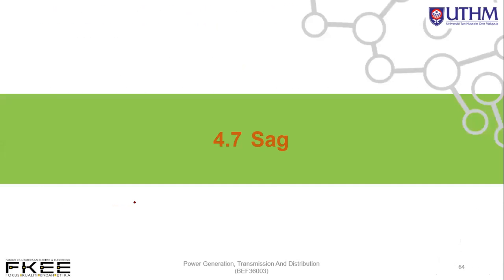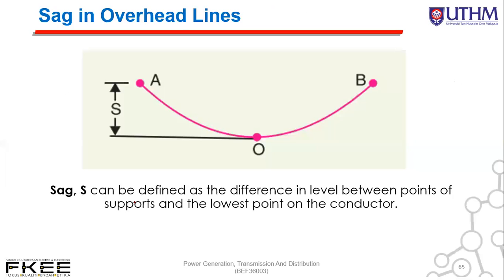Now we look at sag. Okay, kendur. Sag ni kita lebih kurang dalam bahasa kita kendur lah. Talian tu, overhead line yang kendur. Okay, kita lihat pada gambar rajah ni, sag can be defined as the difference in level between points of support and the lowest point on the conductor. So katakanlah support dia kat sini ada tower A, yang ini ada tower B. So di antara A dengan B, tengah-tengah ni adalah conductor, purple ni conductor. So berapa banyak dia kendur dipanggil sag lah.